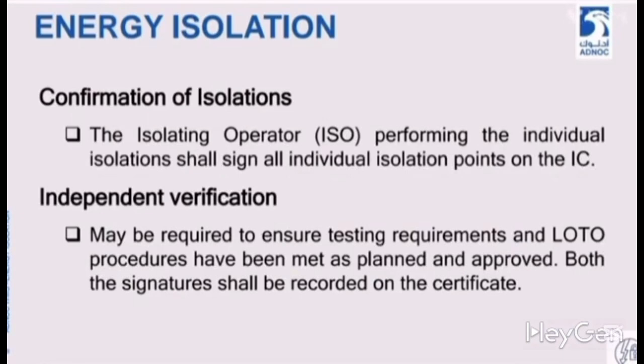Next is the verification. So independent verification of each point will be done by a different person. The operator, who will be the ISO, will demonstrate zero energy to the job performer, JP. For zero energy demonstration, you can use vents, bleed valves, gauges, or operate an electric component. In independent verification, it is also required to ensure testing requirements.